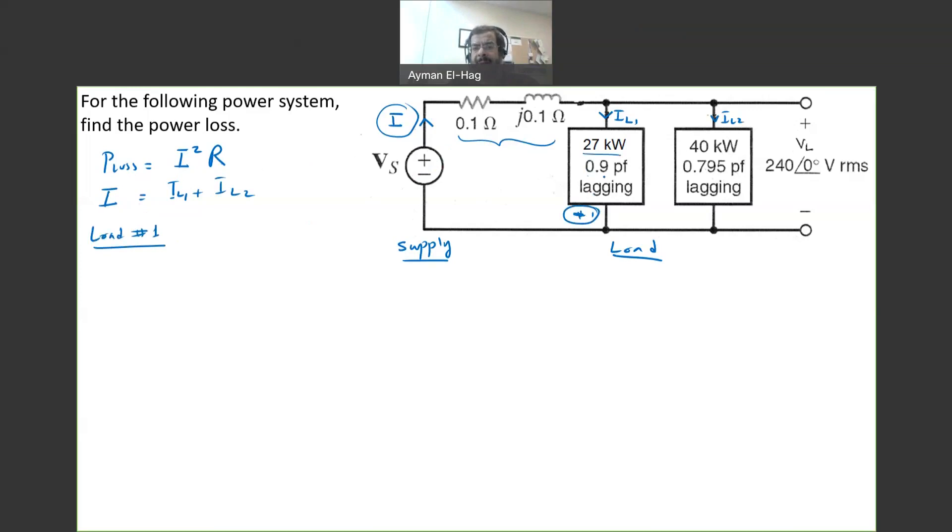We are giving P, the power factor, and it is lagging, and we know the voltage is 240 angle of zero. So, the magnitude of IL1, basically, very straightforward, it is P divided by V times the power factor. So, P is 27,000 divided by 240 times 0.9, and this will give me a current of 125 amps.